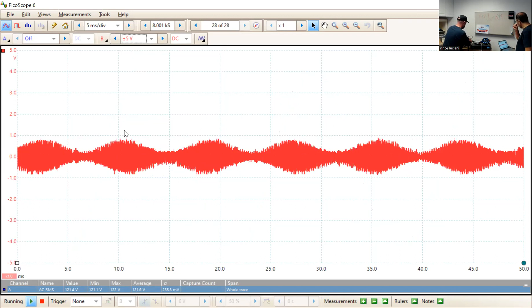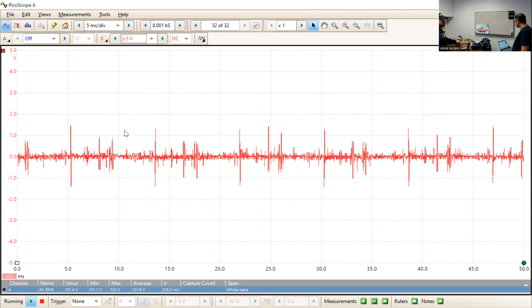I have an isolation transformer. Now, I would have loved to have used the big one, but we didn't have 240 volts. But look how the noise just gets deadened when you go through an isolation transformer. So we'll go back to the first one. You see that red trace there, that's all the noise. And go back to the isolation transformer, and the noise floor goes to near zero.